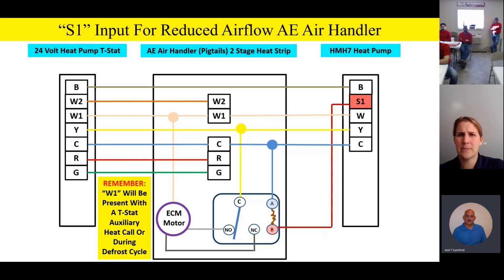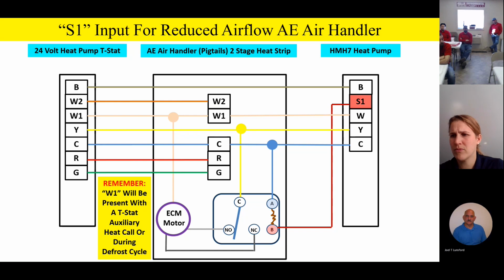So any questions or comments on the logic of the relay and how all that works on the indoor and the outdoor product before we start looking at some other block wiring diagrams to consider? Everybody good? So anytime the auxiliary heat is energized, we're going to lose the variable speed in the 35 to 100% capacity that the outdoor unit's looking for.